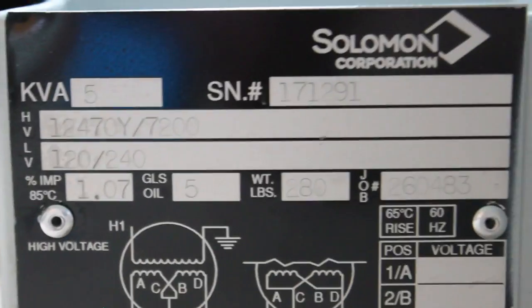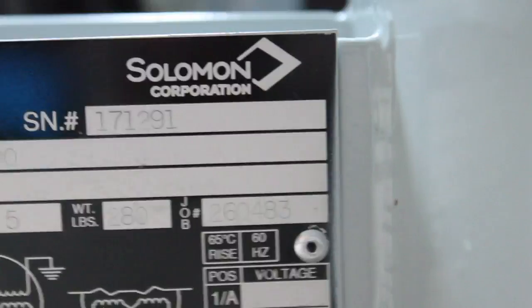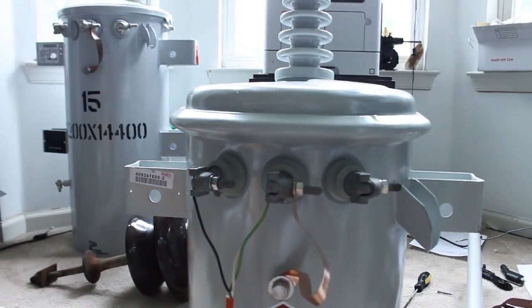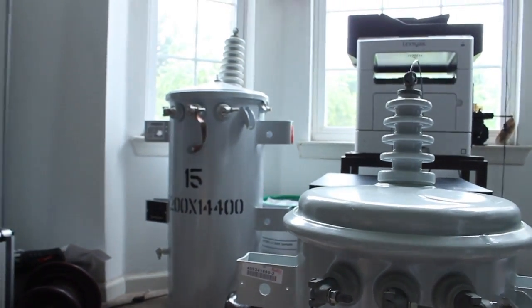The impedance is 1.07, so this will put out approximately, if I'm not wrong, about a couple thousand amps of short circuit current. That one's 2000 amps if you short out the low voltage terminals.